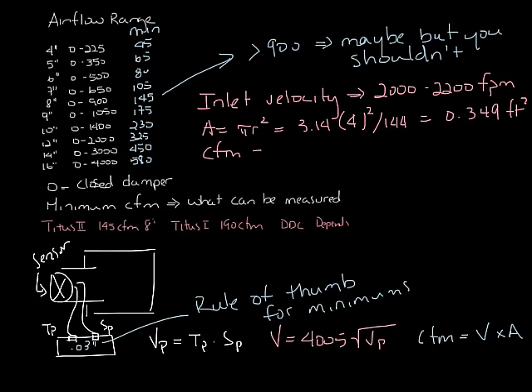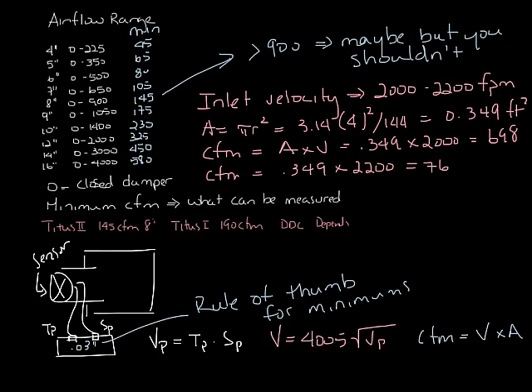From there you can calculate the CFM at 2,000 feet per minute as being 0.349 times 2,000, or 698 CFM. Or at 2,200 feet per minute, which comes out to 768 CFM.